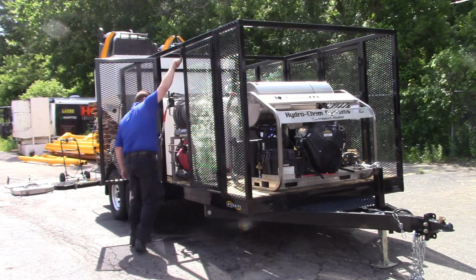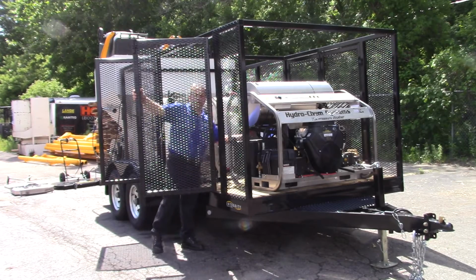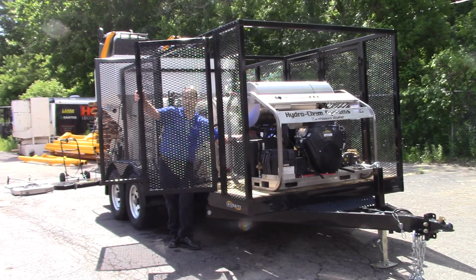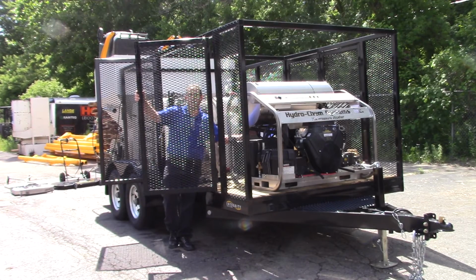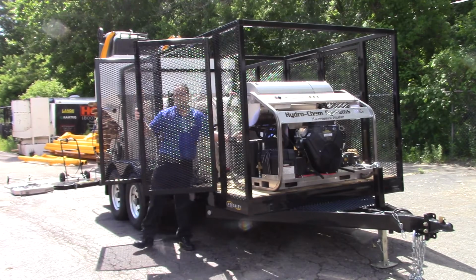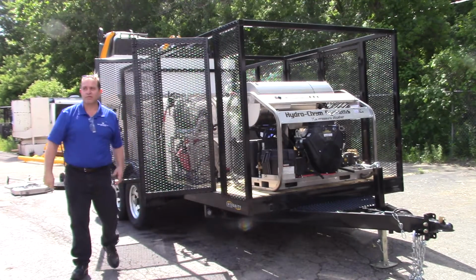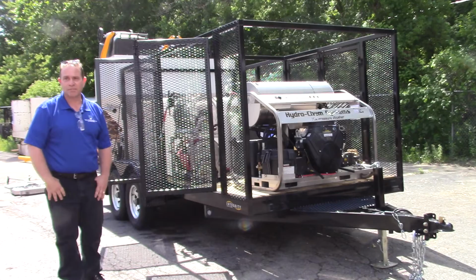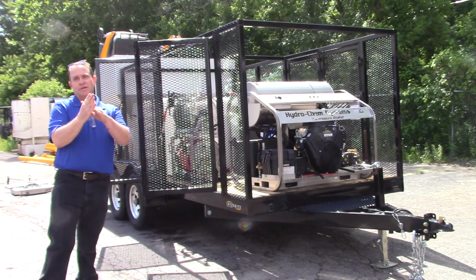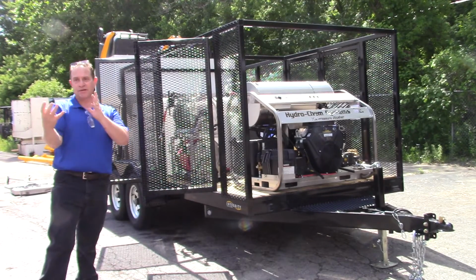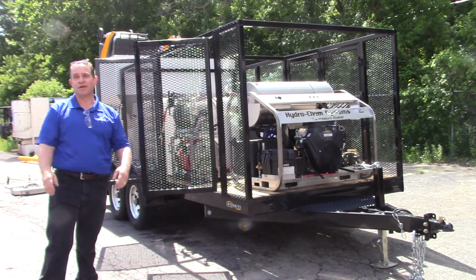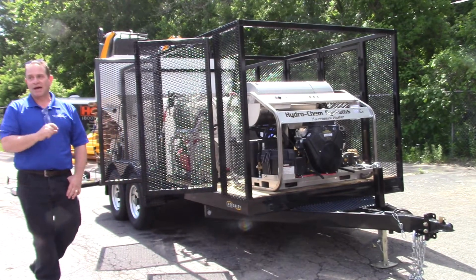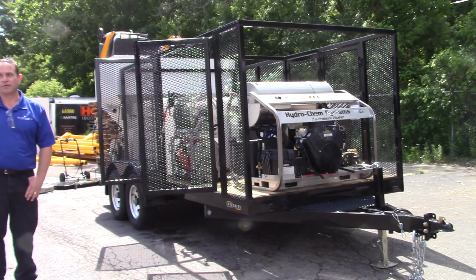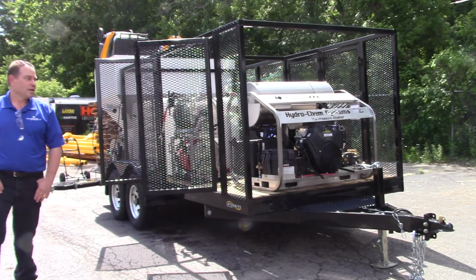Here, looks like a huge, like 2.5 inch or inch hose barb on here. This is actually a steam burst relief valve. This is rated, I think 8,000 PSI or something, 6,000 to 8,000 PSI on the steam burst. It's actually a burst disc. So if that blows out, it just blows the disc out. You can rebuild it, but no one's going to go any further with that. The steam burst relief valve, or steam diaphragm too, they call it.